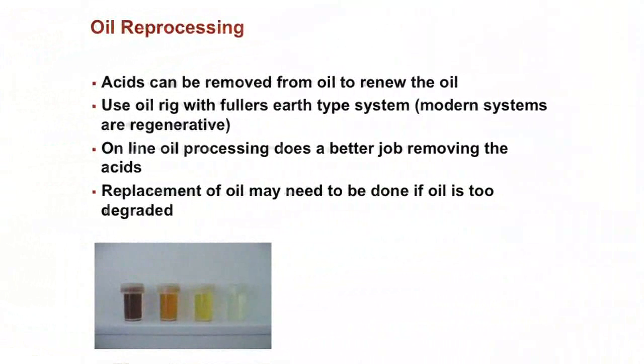And to give you some idea what the oil looks like, brand new oil is actually transparent. It almost looks like water. Then as oil ages, either because of thermal aging of the oil or because sludge is coming out of the windings, it starts to become a lot browner. And very aged oil is almost the color of syrup. So after you process the oil, it comes back to looking clear. This is something you might contemplate doing at midlife of a transformer, when it's, say, 25 or 30 years old.